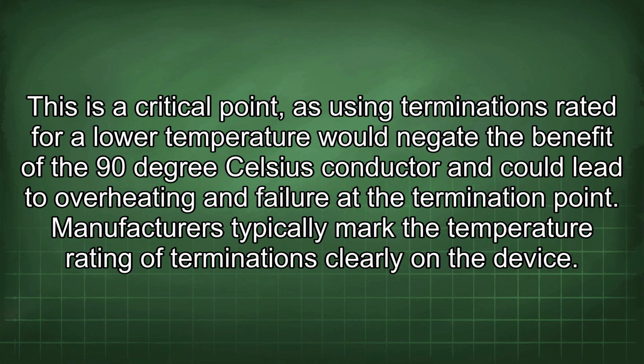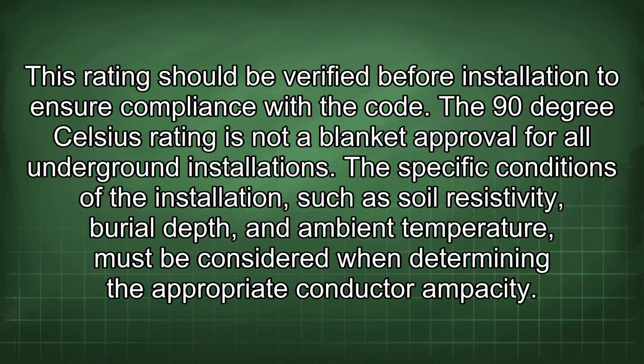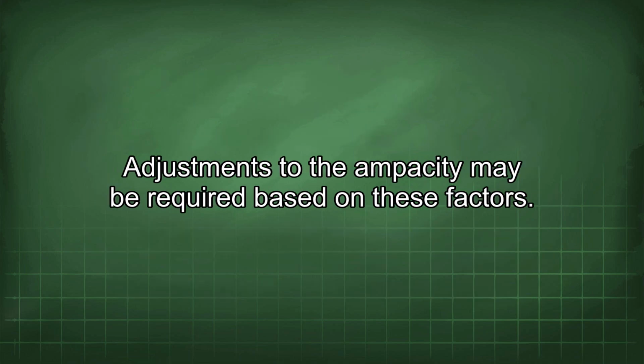Manufacturers typically mark the temperature rating of terminations clearly on the device. This rating should be verified before installation to ensure compliance with the code. The 90°C rating is not a blanket approval for all underground installations. The specific conditions of the installation, such as soil resistivity, burial depth, and ambient temperature, must be considered when determining the appropriate conductor ampacity. Adjustments to the ampacity may be required based on these factors.